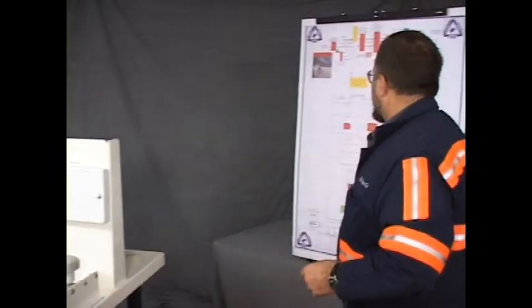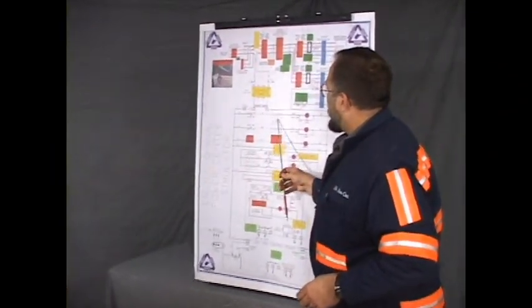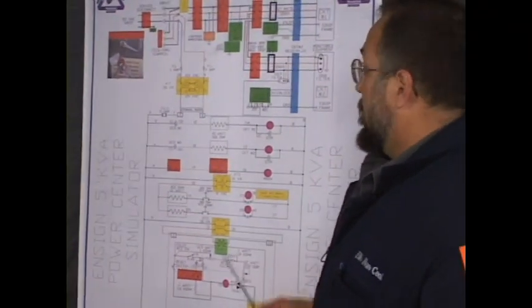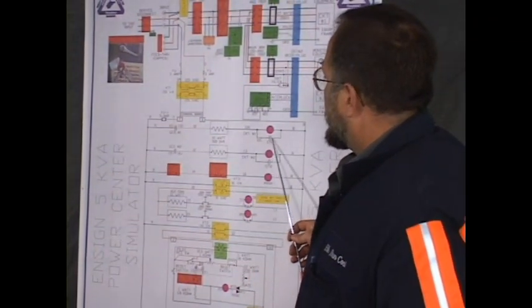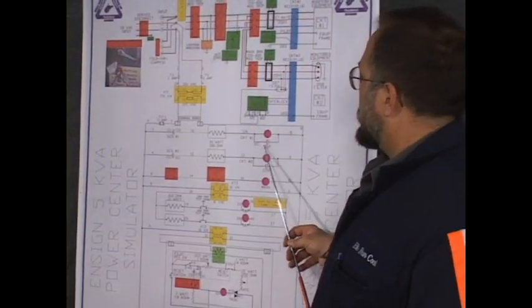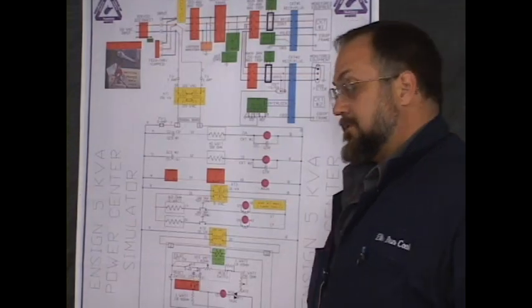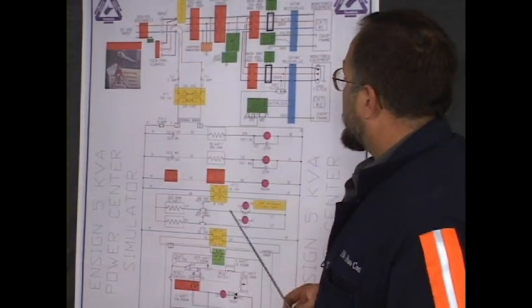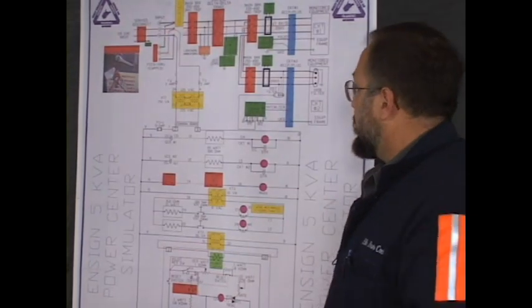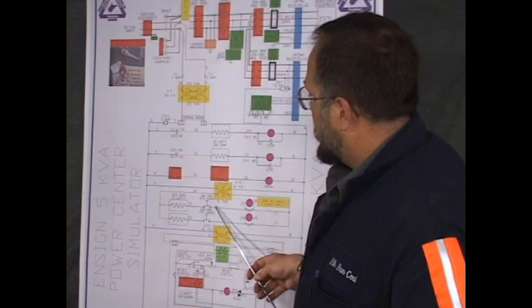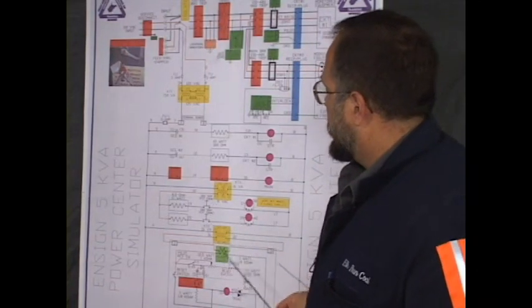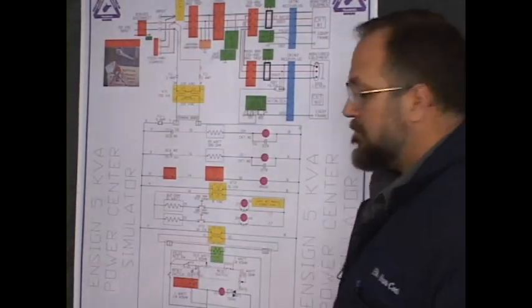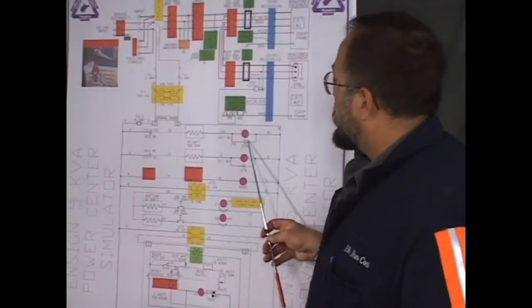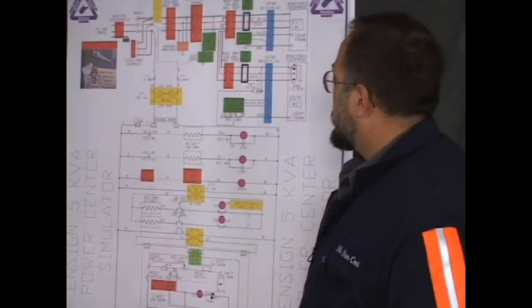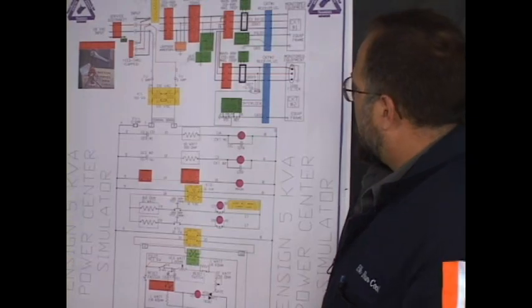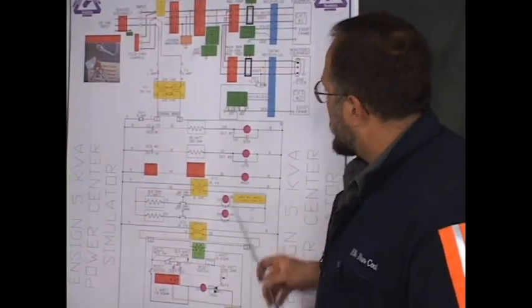there are only 2 points that can cause this particular symptom. All of our power being dropped on a 40-watt 500 ohm resistor. The only way that can do that is if the GTR, the normally open GTR contact, is closed. Now, a ground fault on the system would close that GTR, but you'd have to have the breaker energized, and it would close it only for an instant, and then it would be open again. The ground trip test switch could have failed in a shorted position, keeping it in a test mode, causing it to be closed all the time, or the actual relay itself could have failed and be shorted closed. So we're going to test this ground trip test switch and the GTR.